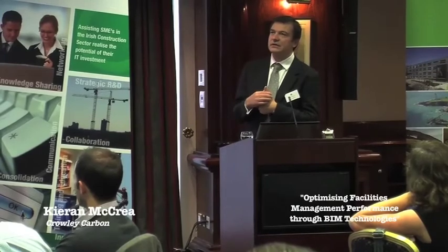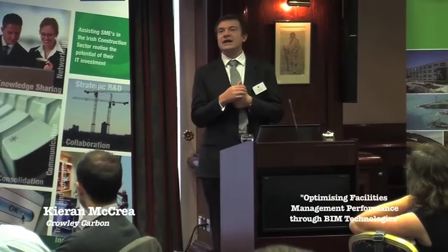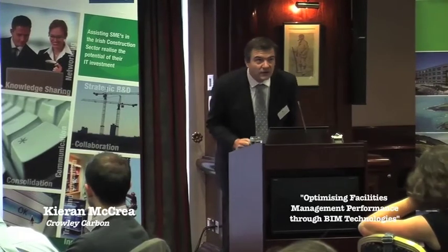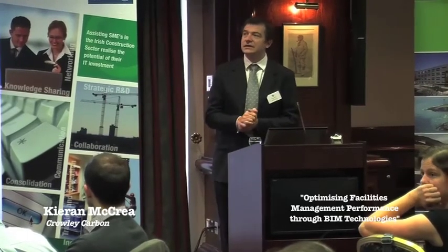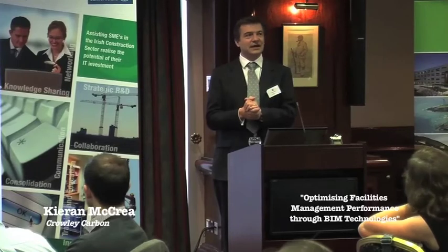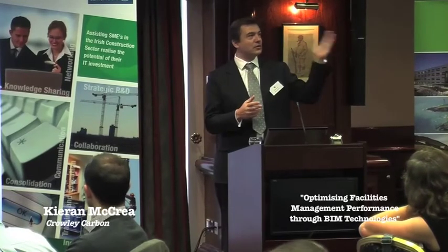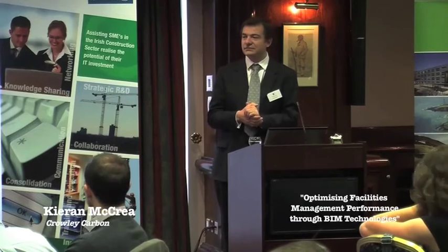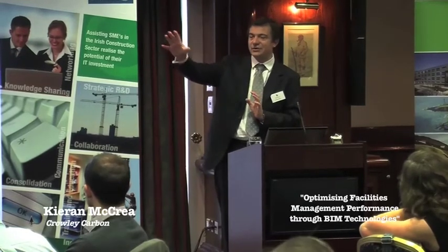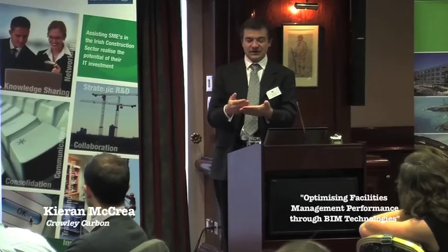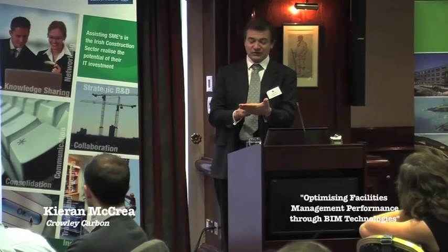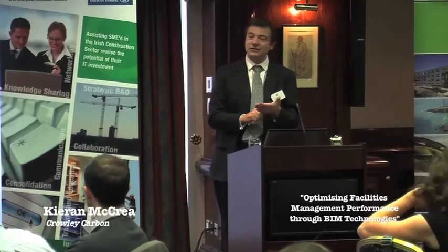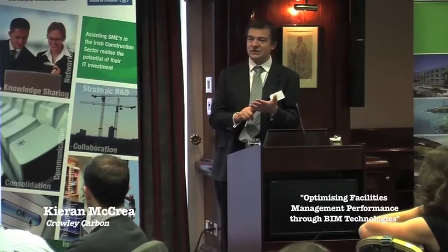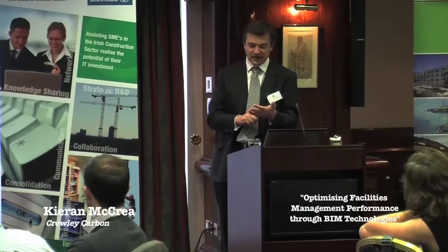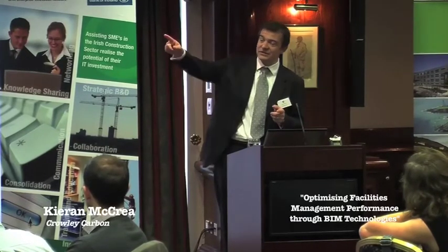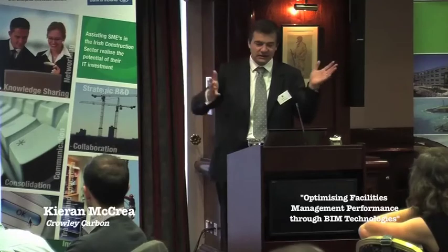I'll use this as an example again: say you've got about 12 fan coil units. It'll look at that and say no matter what time of year, there's always 4 fan coil units heating, even when the majority of the rest are in cooling mode. Then it gives you a list, saying this month your maintenance guys should look at those fan coil units, because they shouldn't be heating all the time, they're obviously fighting - heating up while others are cooling down. So you get a system that's unbalanced and fighting against itself.